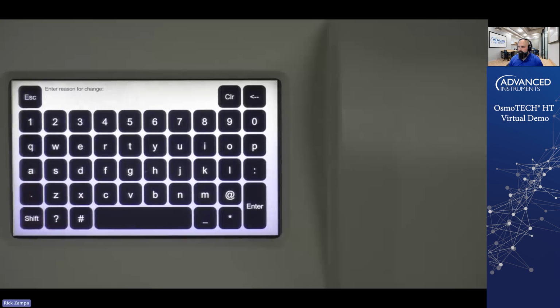It's very important. Part of the audit trail system is a reason for changing something in the system. This is an optional item, but I always recommend that customers turn it on, because if you ever get audited and the auditor looks at the instrument and says, hey, why did you make this change on June 24th in 2025, and this is December or maybe next year, you'll have to go back and try and figure out why you made that change.